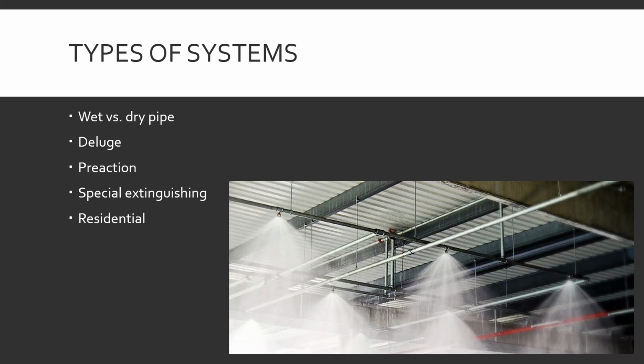No damage done. But they're designed in such a way so that if a sprinkler head's broken, the little countdown starts. After a while, if no one says, hey, it's cool, don't send water into the system, it'll err on the side of caution and water goes into the system. But there's time to cancel the false alarm kind of thing.